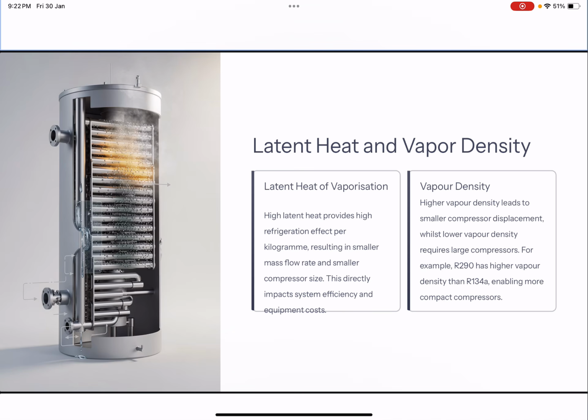If the specific volume is higher, then we will have to have larger compressors. So generally, when we are talking about small capacity compressors or small size compressors, and you are aiming for small size compressors, then we need to go for refrigerants which have a higher vapor density or a lower specific volume. For example, R290 has a higher vapor density than R134A, and hence we need to use more compact compressors with R290 as compared to R134A.